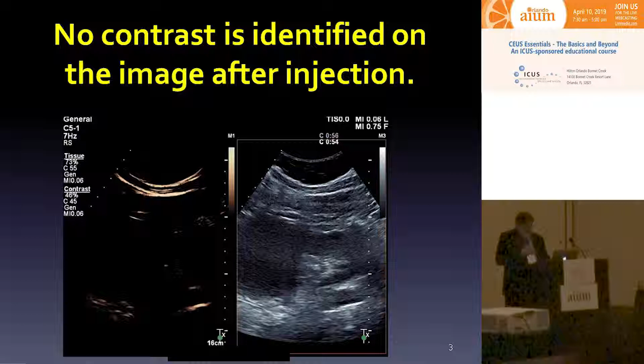So, number one, make sure the contrast agent was injected. If you actually picked up two salines instead of a contrast, remember that. Make sure that the contrast agent was completely activated or shaken. Sometimes you drop the agent, something happens, the sonographer loses the lesion and you have to wait. You look at it, take the syringe off and shake it up to make sure those bubbles are nice and shaken. The IV infiltrated. Make sure that the clamp on the extension tubing is open. Make sure that the contrast setting is on and you're not using high MI.